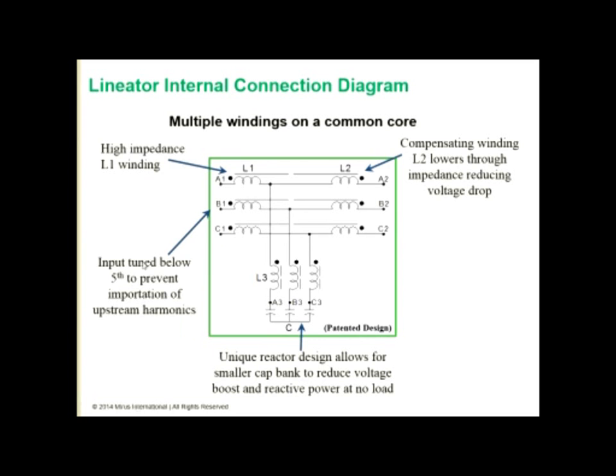On the input, the filter is tuned below the fifth to prevent the importation of upstream harmonics. So the harmonics that we'll see in our power systems on a three-phase system are typically going to be fifth harmonic or higher. So by tuning below the fifth harmonic, we will prevent importation of these harmonics into the filter. And on the output side, it's tuned around the seventh harmonic to remove the harmonics generated by the load or the VFD.